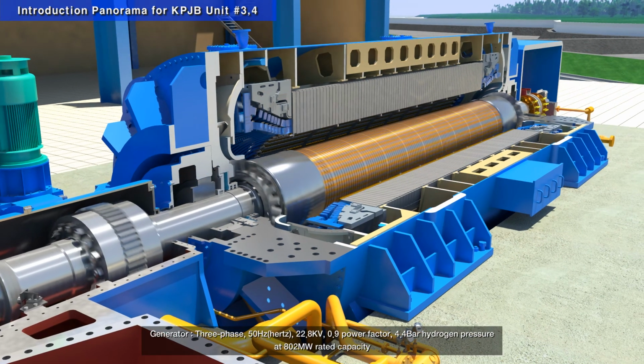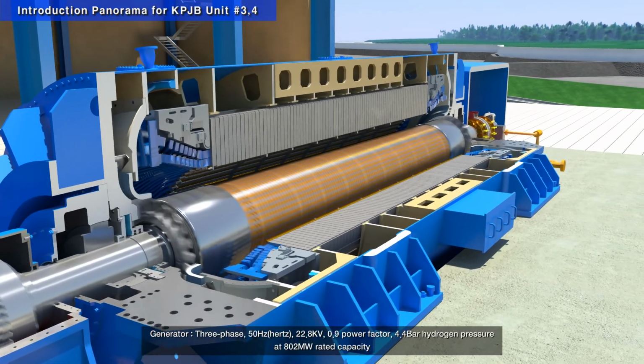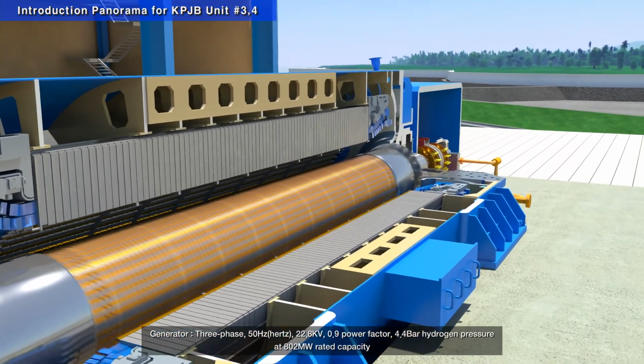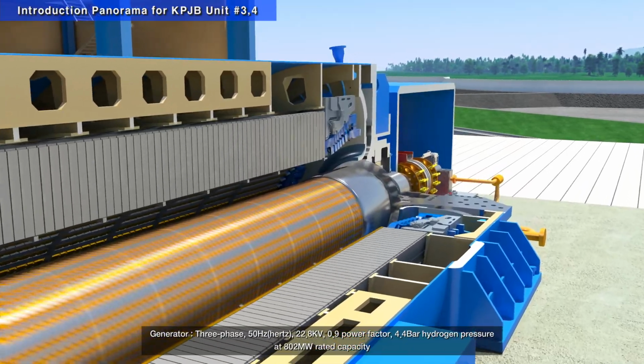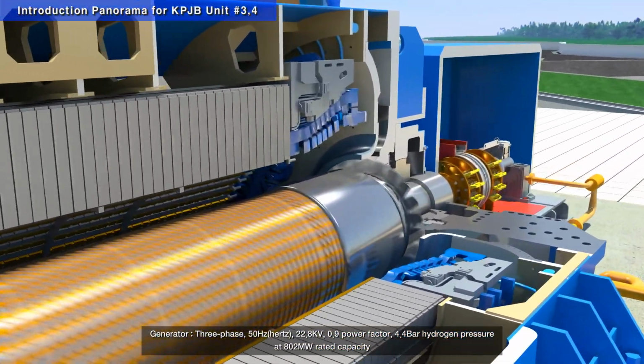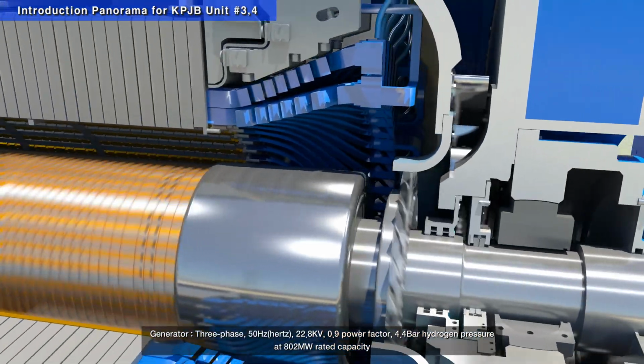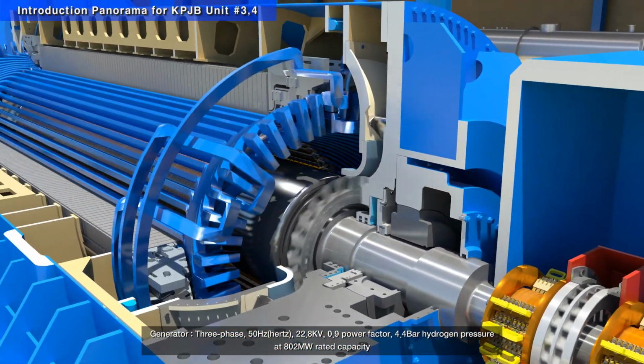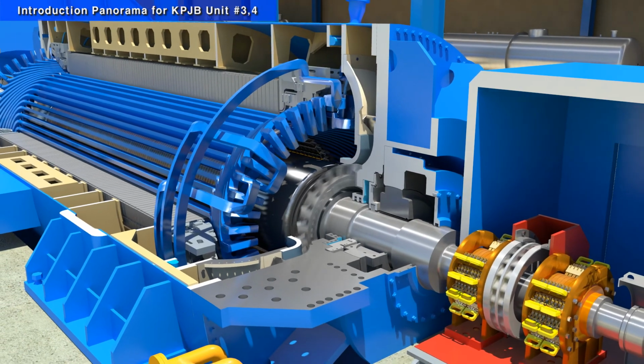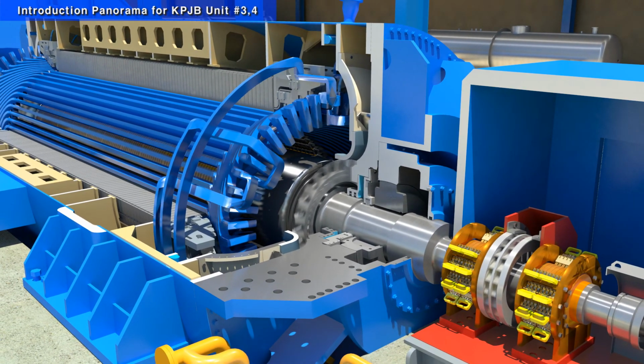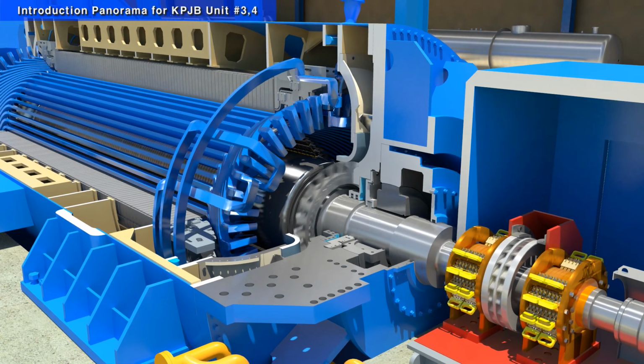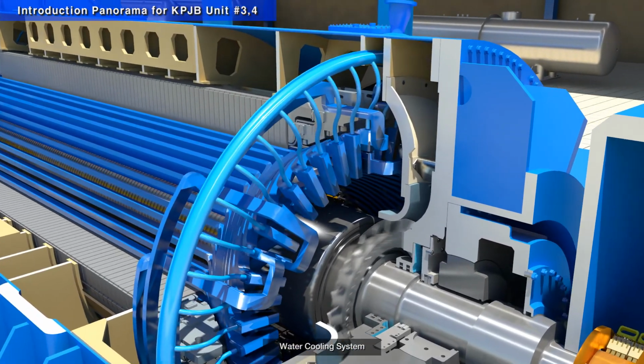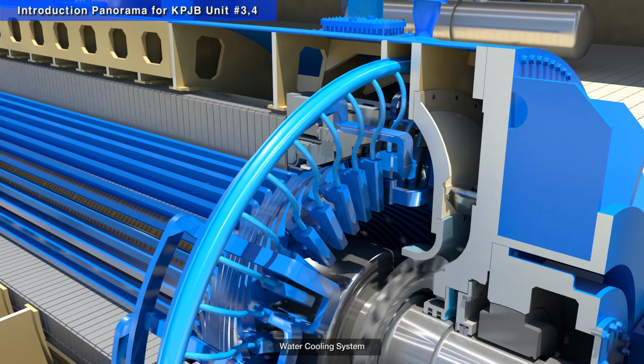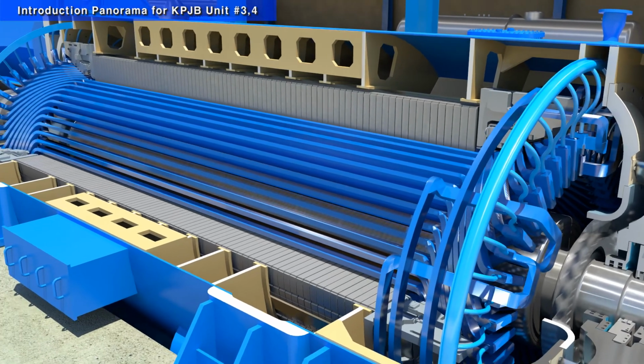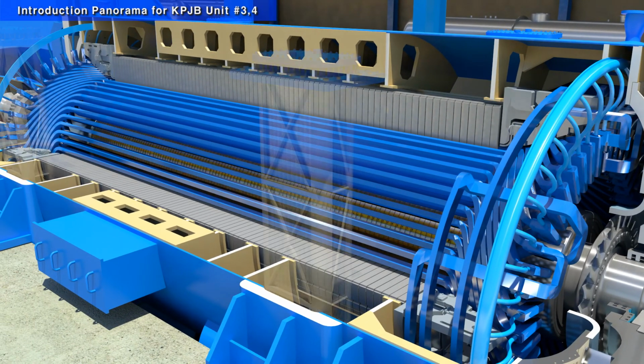The generator is directly connected to the turbine shaft and rotates at 3,000 RPM. It has 3-phase, 50 Hz, 22.8 kilovolts, 0.9 power factor, 4.4 bar hydrogen pressure at 802 megawatts rated capacity. Water is used for stator winding cooling, while hydrogen is used for the generator rotor cooling, and the ventilation is done by the axial flow fan, which is connected to the rotor shaft.